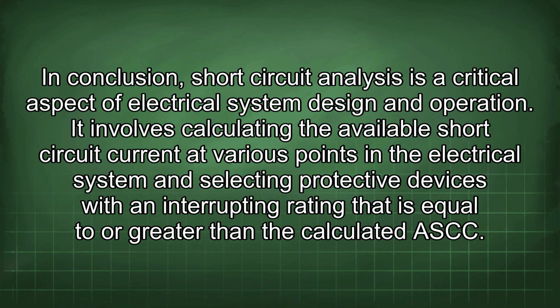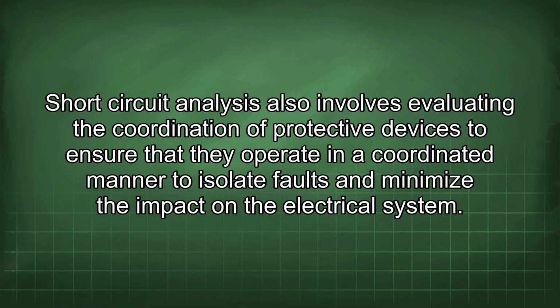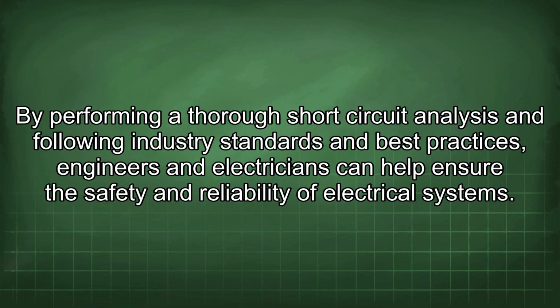In conclusion, short-circuit analysis is a critical aspect of electrical system design and operation. It involves calculating the available short-circuit current at various points in the electrical system and selecting protective devices with an interrupting rating that is equal to or greater than the calculated ASCC. Short-circuit analysis also involves evaluating the coordination of protective devices to ensure that they operate in a coordinated manner to isolate faults and minimize the impact on the electrical system. By performing a thorough short-circuit analysis and following industry standards and best practices, engineers and electricians can help ensure the safety and reliability of electrical systems.